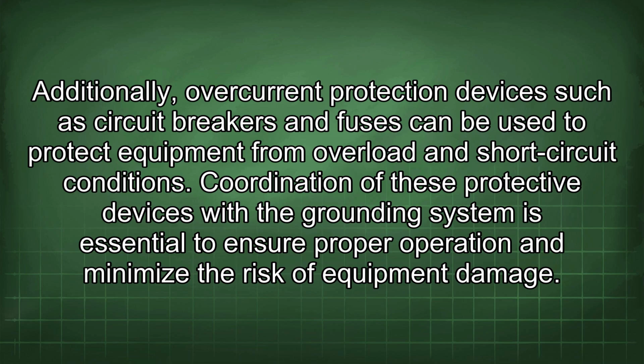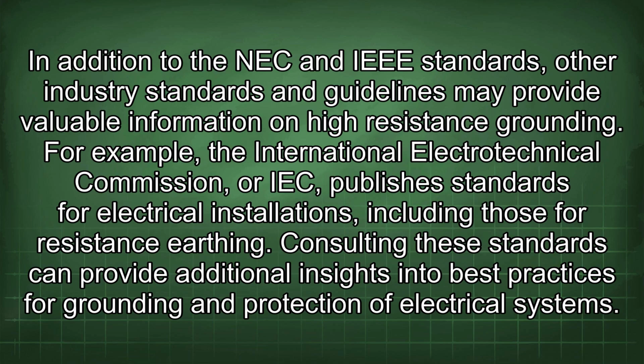Coordination of these protective devices with the grounding system is essential to ensure proper operation and minimize the risk of equipment damage. In addition to the NEC and IEEE standards, other industry standards and guidelines may provide valuable information on high-resistance grounding. For example, the International Electrotechnical Commission, or IEC, publishes standards for electrical installations, including those for resistance earthing. Consulting these standards can provide additional insights into best practices for grounding and protection of electrical systems.